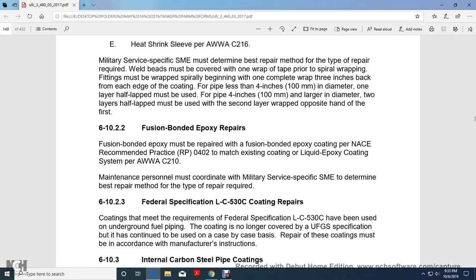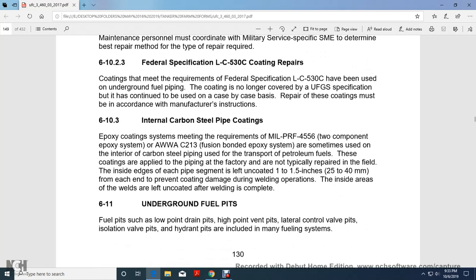Weld beads must be covered with one wrap of tape prior to the spiral wrapping. The fitting must be wrapped spirally, beginning with one complete wrap within 3 inches back of the edge of the coating. For pipelines less than 4 inches in diameter, one layer half lap must be used. For pipe 4 inches or larger in diameter, two layers half lap must be used, with the second layer wrapped opposite hand of the first.